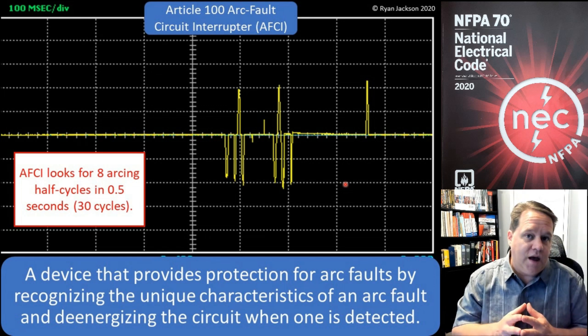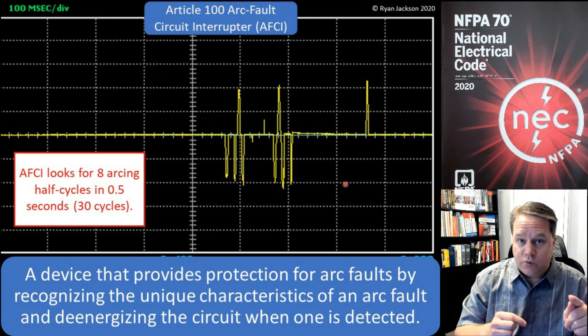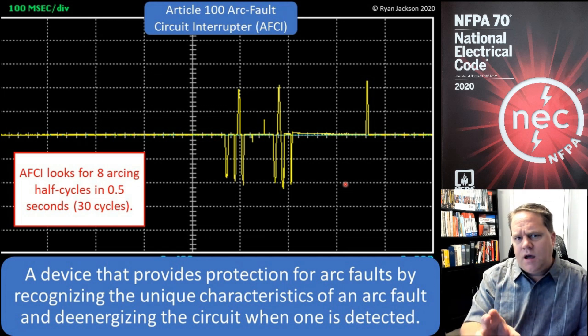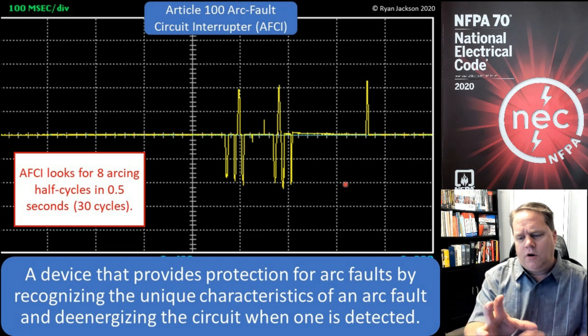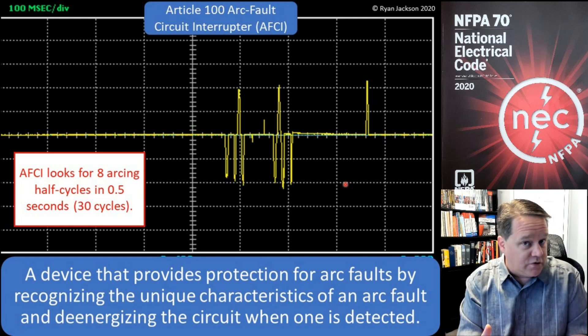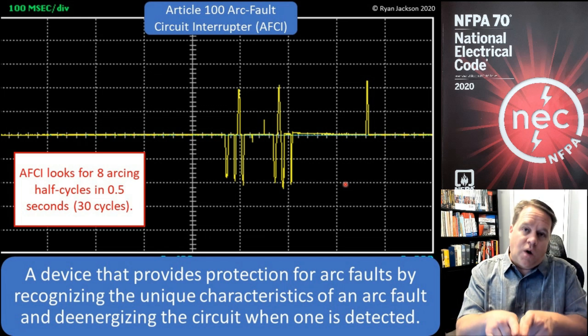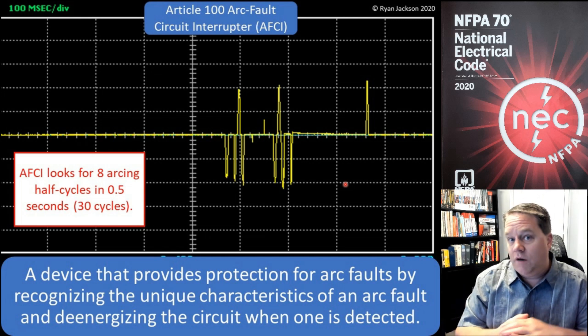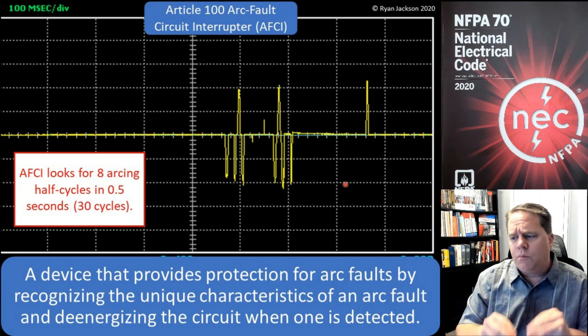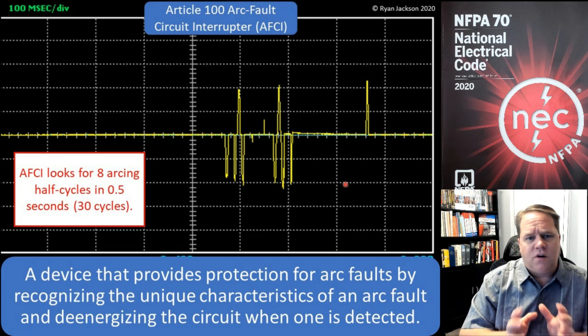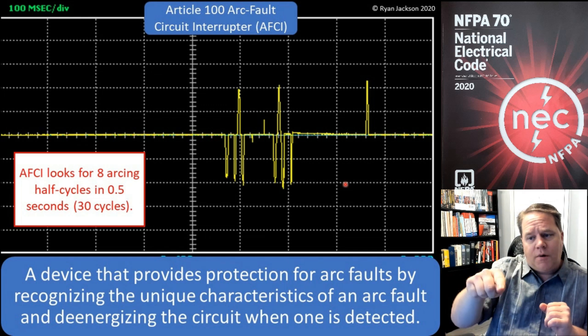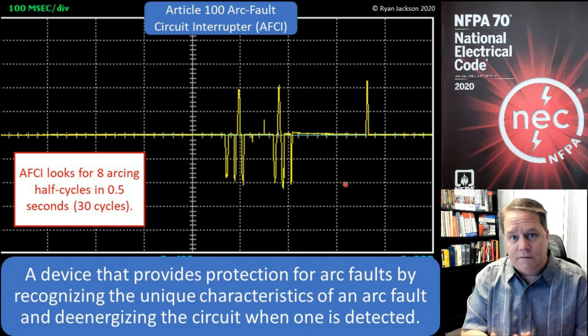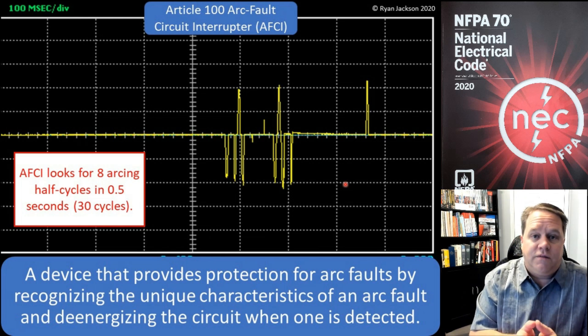There aren't a lot of appliances in a house at 120V on 15 and 20-amp circuits that pull five amps, so usually an AFCI is looking for arcs happening inside the walls or in a two-wire cord — usually a parallel arc. It does sense series arcs as well, ever since 2008, but it's more focused on arcs inside the walls: counting how many happen, looking at the current of those arcs, and opening in the event of an arc fault.